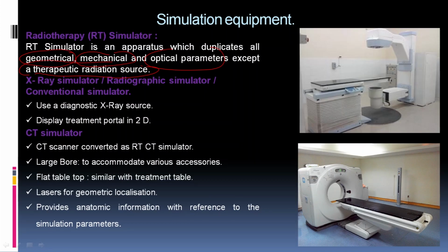Broadly we can divide simulators into two types. One is the X-ray simulator, also known as the radiographic or conventional simulator, where a diagnostic X-ray source is used and displays the treatment portal in two dimensions.